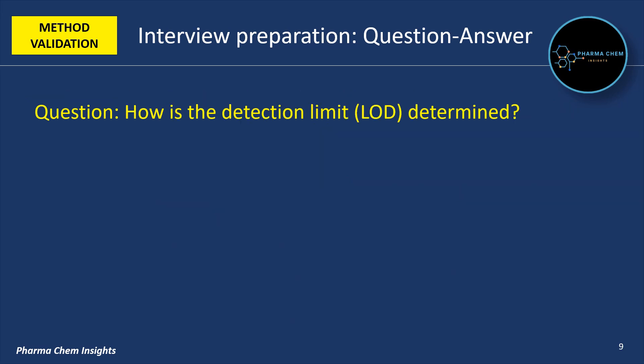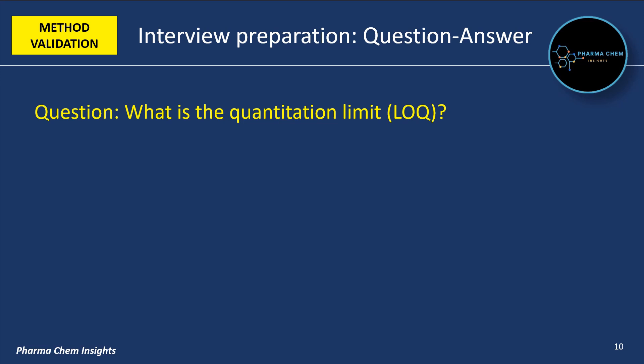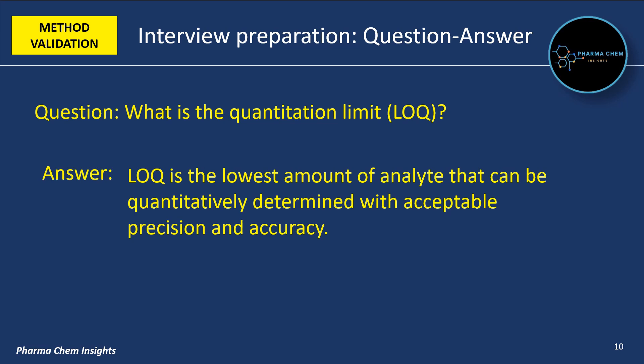Next question: how is the detection limit LOD determined? The limit of detection LOD is determined by analyzing samples with known low concentrations of the analyte and establishing the minimum level at which the analyte can be reliably detected but not necessarily quantified. Next question: what is the quantitation limit LOQ? The limit of quantitation LOQ is the lowest amount of analyte that can be quantitatively determined with acceptable precision and accuracy.